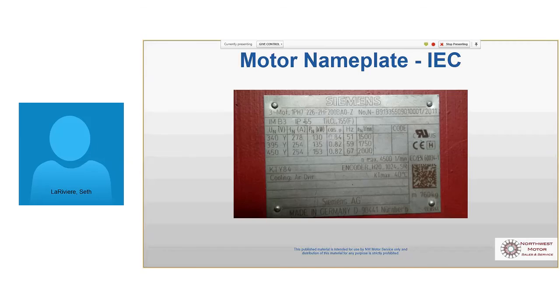And there are some differences. The frame sizes are different. I think one of the advantages that we bring to the party is we have a mechanical PE on staff who spent his entire life in a paper mill on the reliability side, a mechanical engineer. When I'm replacing these metric motors with a NEMA standard, he'll draw me up a nice base that makes all the mounting hole changes, and a plate so the motor is mounted on that plate. Then when the customer goes to install it, they just put the plate and the motor down, pull the old metric, slap in the new US NEMA dimension motor, good to go.